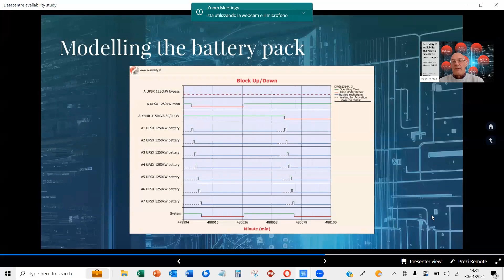So this is the A system transformer, again coming in, and you see that the battery has finished recharging, and then you got the dotted line after the blue line, just to look at it this side. So the battery is now available, and as soon as the failure comes in, it's ready to start covering, or at least for 7 minutes. Then obviously you clearly need a generator if you're not able to recover that. So this was only a test that we did, and we didn't pursue any further.